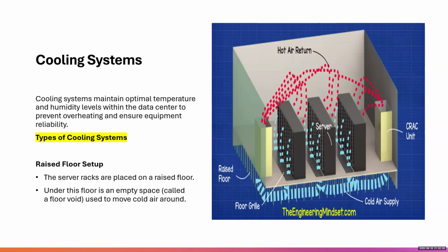One type of cooling is the raised floor setup. In this setup, the server racks sit on a raised floor, and there's an empty space under the floor called the floor void. Cold air flows through this space and rises up to keep the servers cool. It's one of the most common methods used in a data center.